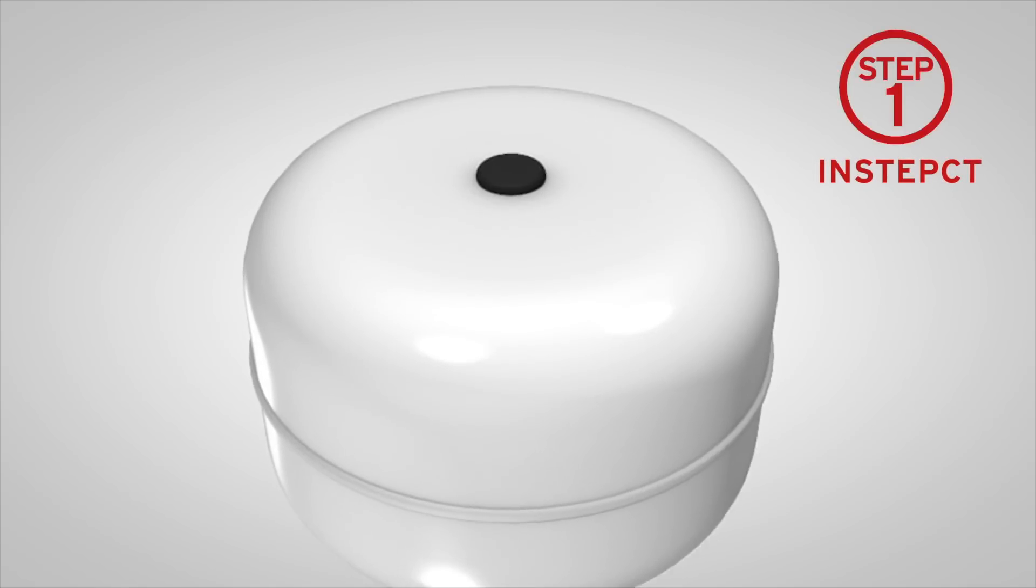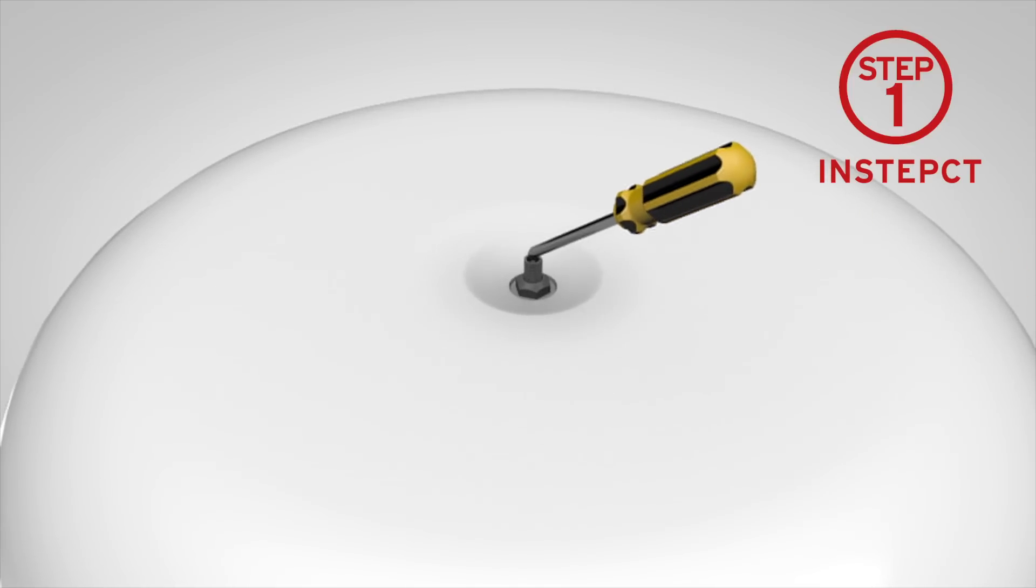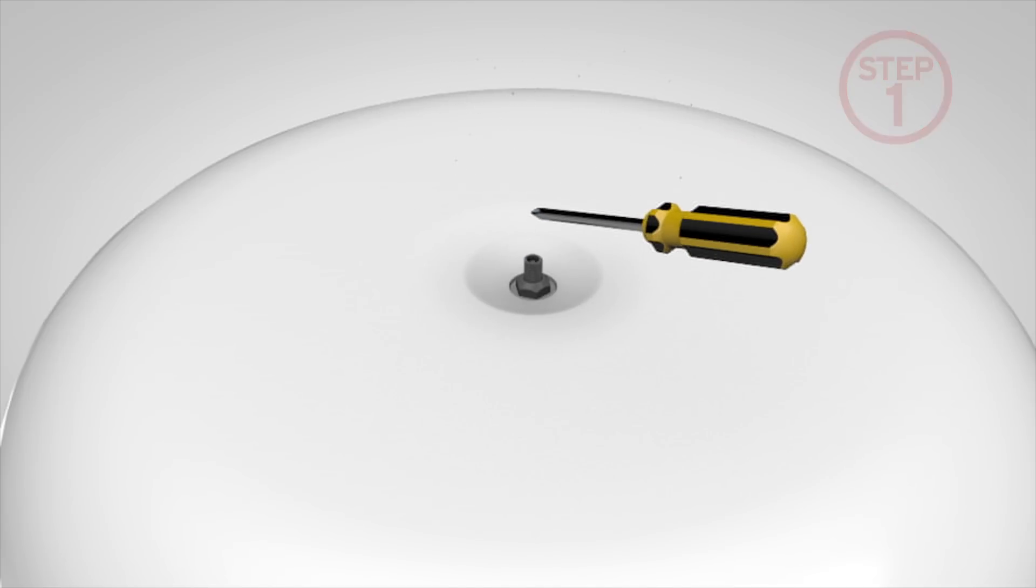Pressing down the Schrader valve is a simple way of checking the integrity of the rubber diaphragm. If water comes out, the diaphragm has failed and the vessel will need replacing.